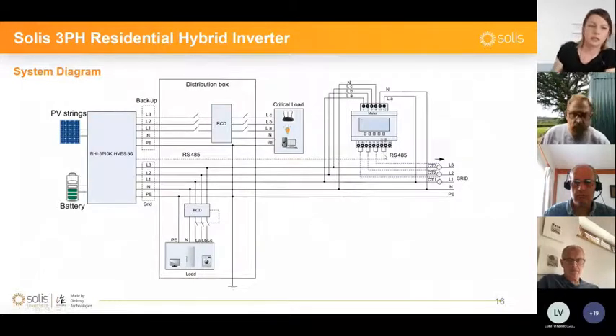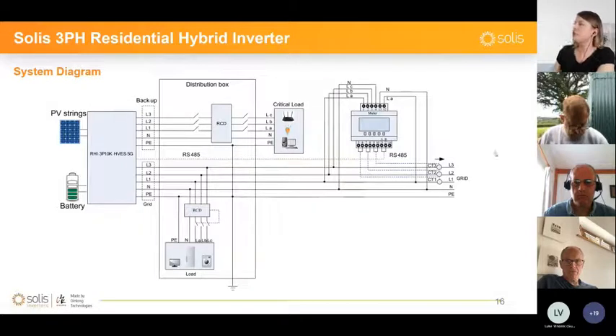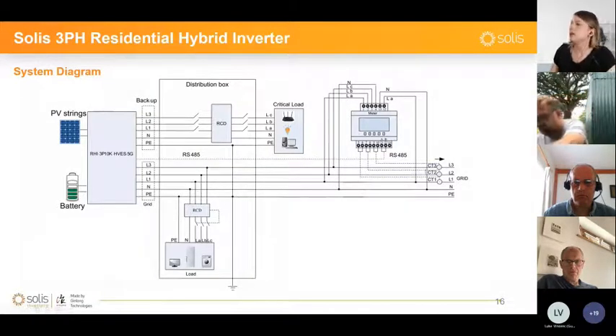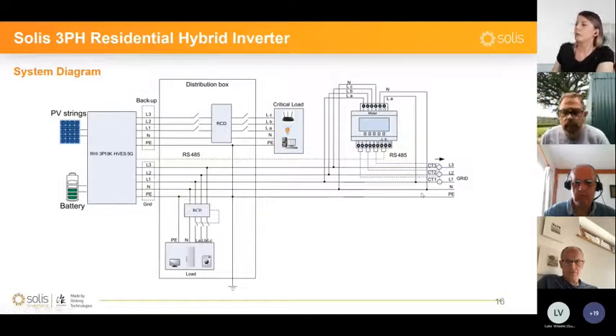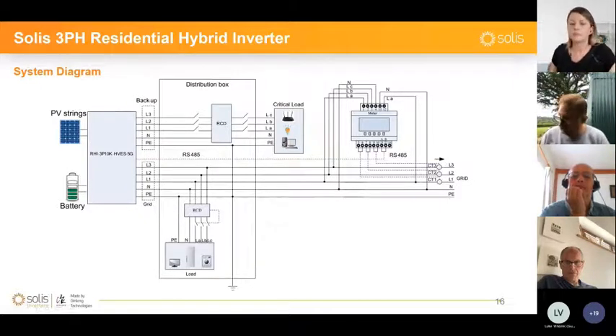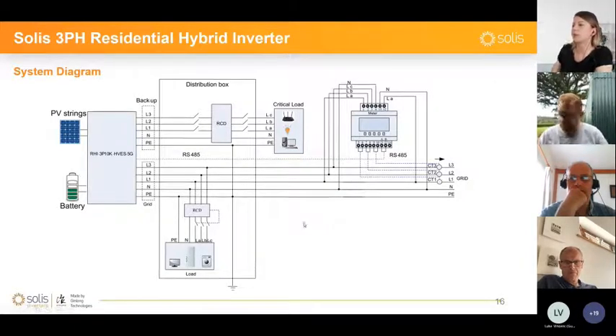I haven't added this for the single phase, but I'm going to mention it now because it's really, really important. These cables that you would be connecting the CT clamps with should never be extended. So this meter should always be installed on the main AC incoming power supply. And you can extend the RS485 cable that connects the meter to the hybrid inverter. It's really crucial that you do not extend the cables for the CT clamps, because I think the maximum length is, I don't know, somewhere about 10 meters. If you extend them to more than that, it will lose the signal and the meter will get no information from the CT clamps.